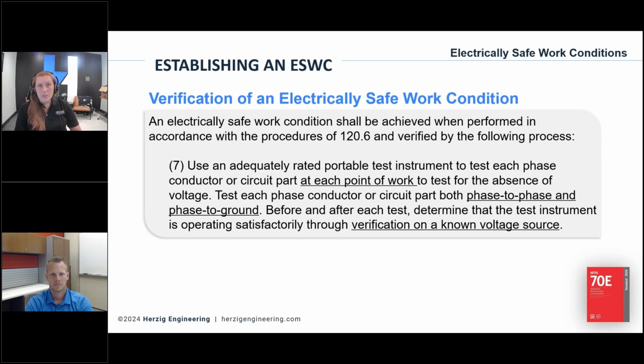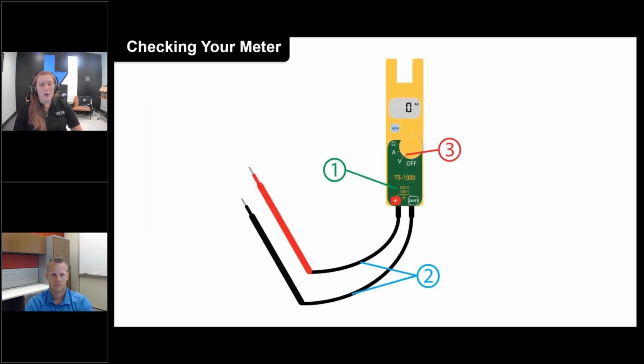Before and after each test, determine that the test instrument is operating satisfactorily through verification on a known voltage source. In other words, make sure your meter's still working. So it's a live check, then you check phase to ground where you're working, back to the live known source, and get a reading that you would expect. We'll dive into that a little more in a moment, but for now, first of all, double check that the meter is the right rating.